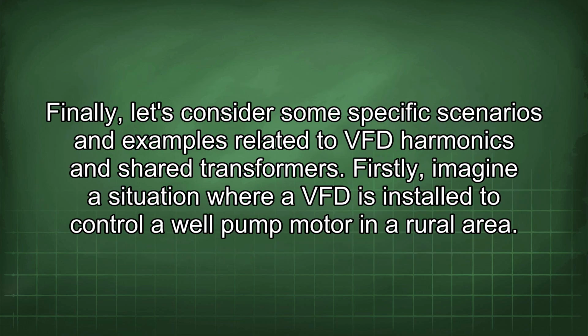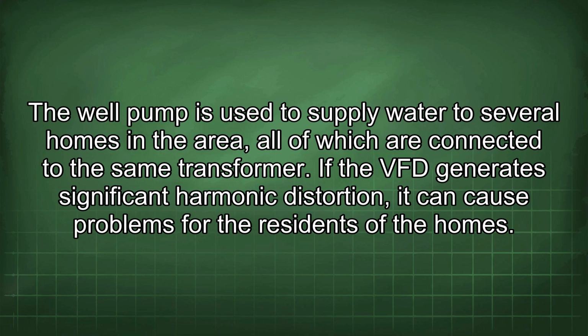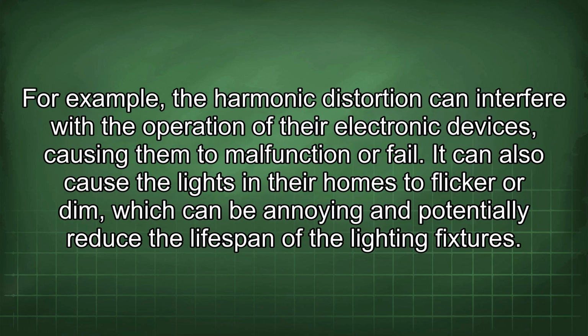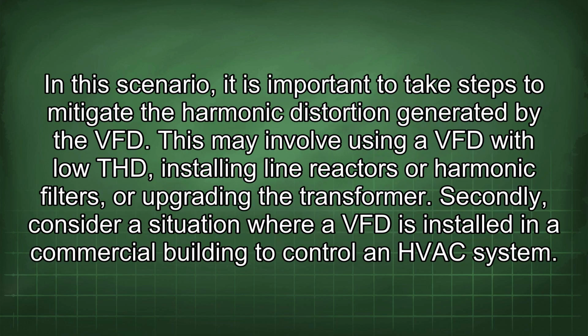Finally, let's consider some specific scenarios and examples related to VFD harmonics and shared transformers. Firstly, imagine a situation where a VFD is installed to control a well pump motor in a rural area. The well pump is used to supply water to several homes in the area, all of which are connected to the same transformer. If the VFD generates significant harmonic distortion, it can cause problems for the residents of the homes. For example, the harmonic distortion can interfere with the operation of their electronic devices, causing them to malfunction or fail. It can also cause the lights in their homes to flicker or dim, which can be annoying and potentially reduce the lifespan of the lighting fixtures. In this scenario, it is important to take steps to mitigate the harmonic distortion generated by the VFD. This may involve using a VFD with low THD, installing line reactors or harmonic filters, or upgrading the transformer.